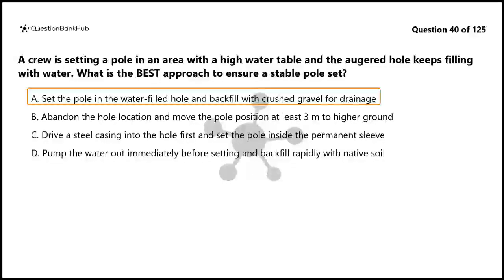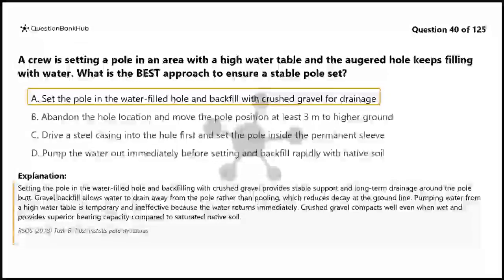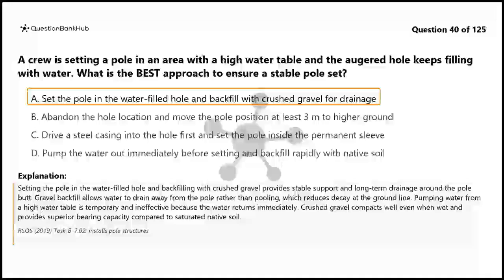The correct answer is A. Setting the pole in the water-filled hole and backfilling with crushed gravel provides stable support and long-term drainage around the pole butt. Gravel backfill allows water to drain away from the pole rather than pooling, which reduces decay at the ground line. Pumping water from a high water table is temporary and ineffective because the water returns immediately. Crushed gravel compacts well even when wet and provides superior bearing capacity compared to saturated native soil.